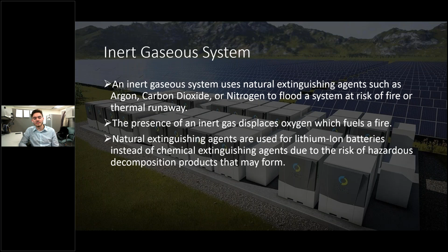Inert gaseous systems. An inert gaseous system uses natural extinguishing agents such as argon, carbon dioxide, and nitrogen to flood a system at risk of fire and thermal runaway. The presence of an inert gas displaces oxygen, which fuels a fire. Natural extinguishing agents are used for lithium-ion batteries instead of chemical extinguishing agents due to the risk of hazardous decomposition products that may form.